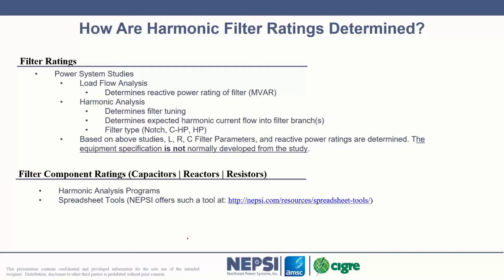So how are filter ratings determined? Power system studies, number one: load flow studies, or some type of load study, and you're coming up with the reactive power rating. After you come up with a reactive power rating, you develop a harmonic analysis. That might be with DIgSILENT, I think is maybe the primary software used in Australia, but there are other programs like ETAP, EasyPower, SIME, all different types of programs. What is the purpose of harmonic analysis? It is to determine and calculate the voltage and current distortion throughout the entire network, and also to determine the harmonic current that will flow into the harmonic filter, so that you can come up with the filter parameter ratings, L, R, and C.